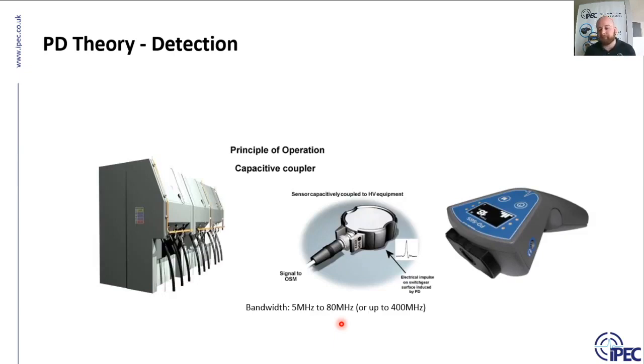Okay, so looking at the switchgear side, on medium voltage switchgear, what we tend to use is CCTEV sensors, as we call them, capacitively coupled sensors. Essentially, they're also more commonly known as just TEV sensors. Many of you will be familiar with TEV devices. Handheld TEV devices have been used in the industry for many, many years. In fact, for many engineers, that's their only familiarity with PD test equipment, if you like.